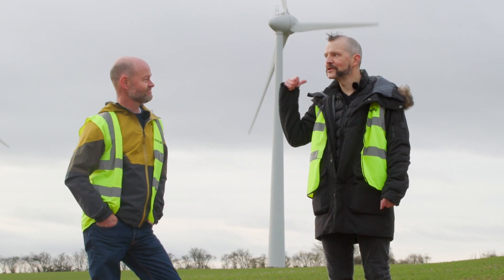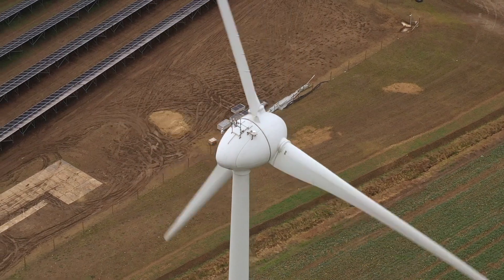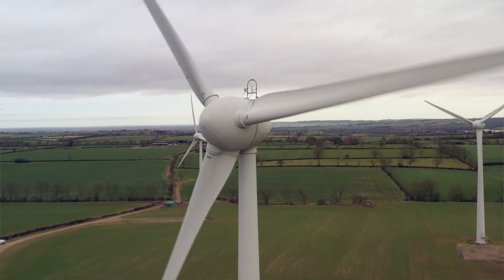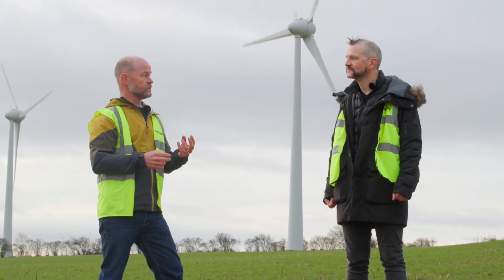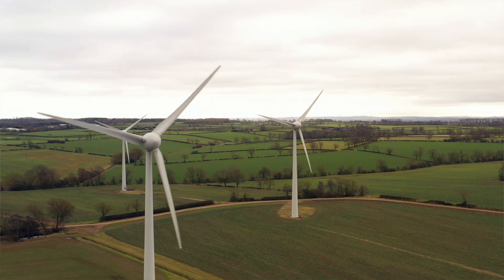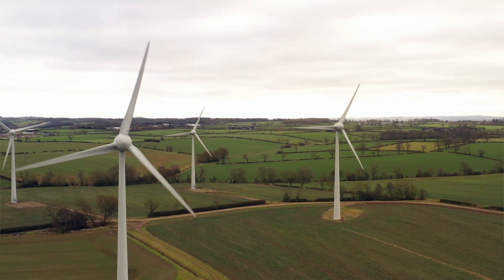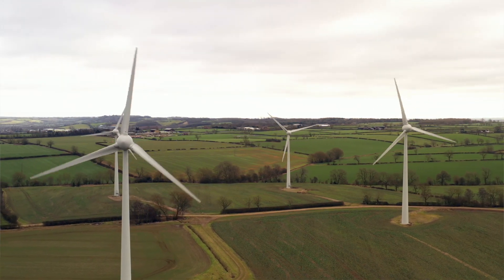How do they know which way the wind blows? On top of each machine is an anemometer — not the old-school type with three spinning cups. There's a more intelligent system: two sensors on the top shine a beam of light that measures particles of dust to see how fast the dust is moving — that gives wind speed — and also which direction the dust is going, which gives the direction the wind is coming from.